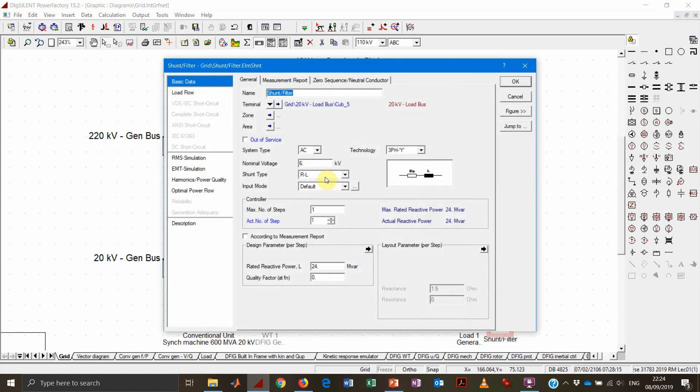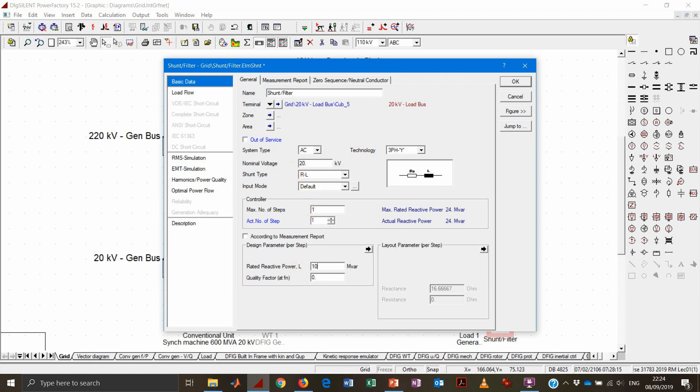So we will connect the inductive shunt, of course, because we want to compensate for the capacitive load. Let's say that we want to design a shunt that has 10 Mvar per step, and actually it has 10 steps, so it can be adjusted.